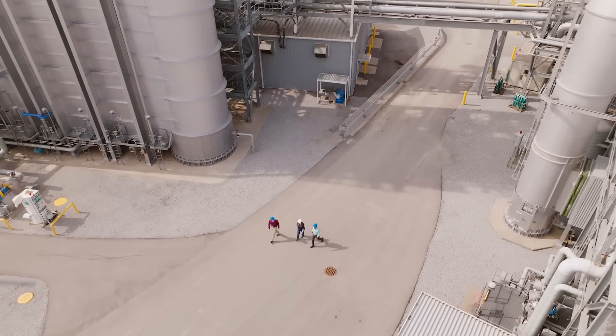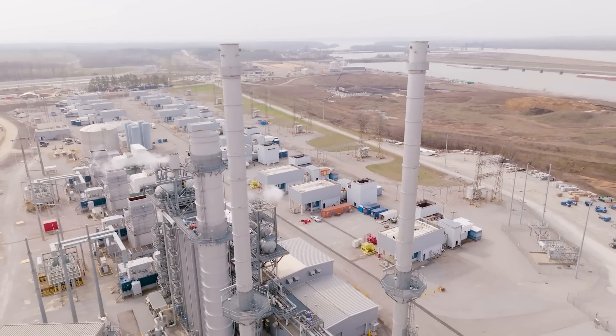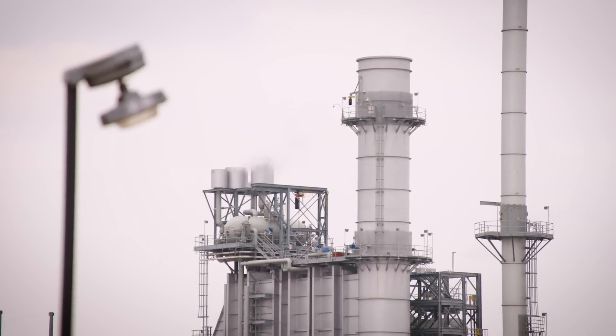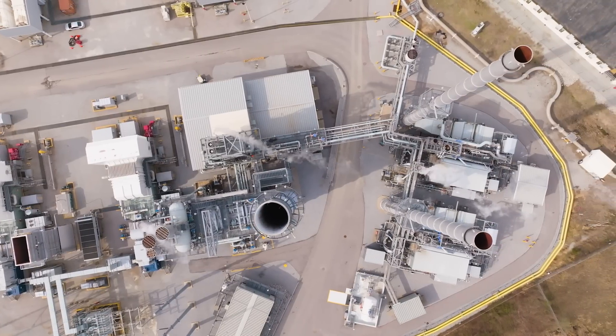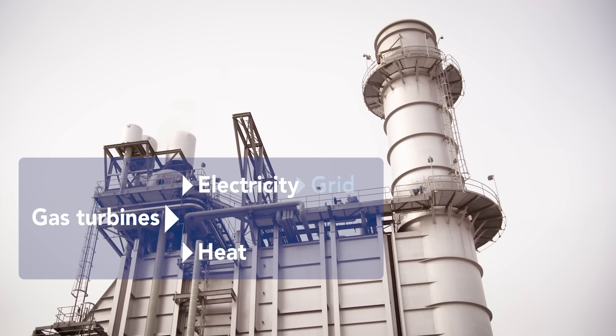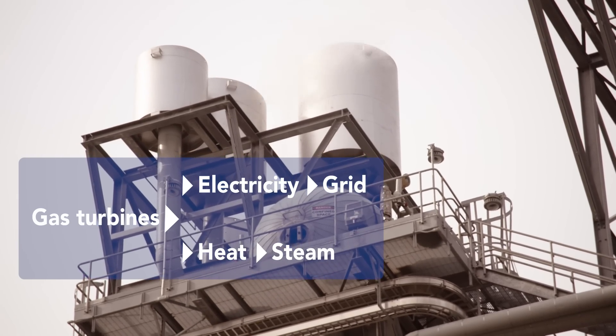What we're looking at today is the combustion turbine unit that provides the Chemours New Johnsonville site with steam. It is a nameplate capacity unit of 600,000 pounds per hour of steam. Steam is pipeline-conveyed from here over to our manufacturing process to make titanium dioxide. With coal being on the way out, we worked with a partnership to have this combustion turbine unit use natural gas to provide steam. The heat recovery steam generator functions to capture all that waste heat that would otherwise just be lost.